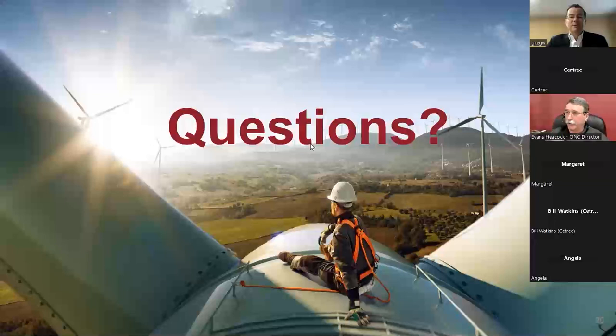Let me start off, since I have a background in nuclear. Nuclear plants have safety and non-safety features. This wouldn't necessarily be used for safety at this time, but you could use it on the non-safety balance-of-plant circuits. As shown in one of the pictures, Greg showed those installs on the front of the switchgear. You could easily put this on the front of non-safety switchgear and have those CTs go in with split CTs very easily from a nuclear power plant standpoint. That's really why I'm excited about this, because it's so easy. You could go into new plants, not necessarily safety related. He hasn't done any of the qualifications for that yet. It doesn't mean it couldn't, but right now it would be a non-safety function.